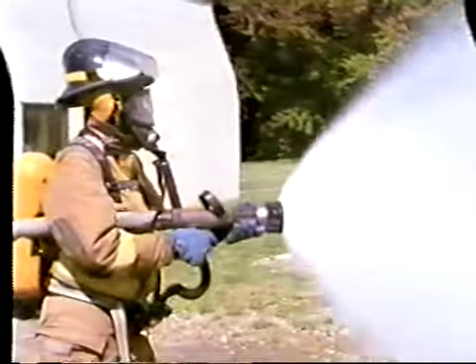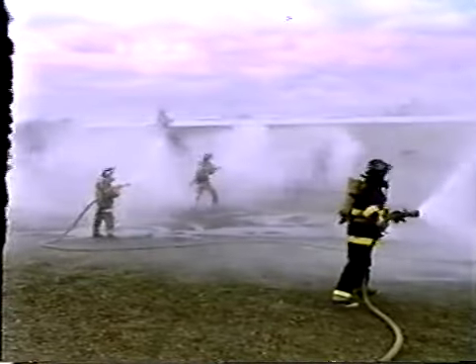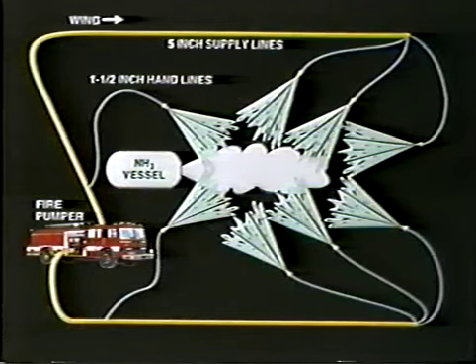In the case of a discharge outside, the greatest danger is the vapor. Anhydrous ammonia vapors are lighter than air but there is the potential for a negatively buoyant plume that lingers near the ground. A lethal concentration of anhydrous ammonia in air is less than 1%, and such an air-vapor mixture may be colorless and also linger near the ground. Theoretically at 32 degrees Fahrenheit, one volume of water will absorb about 1,160 volumes of anhydrous ammonia vapor. Proper application of water fog spray is a proven and effective method of controlling outdoor releases. Pumpers should be positioned upwind and hose lines deployed downwind with nozzles arranged in a semicircle a safe distance from the point of release. The exact distance will depend on wind conditions and the size of the vapor plume. This establishes a water curtain.